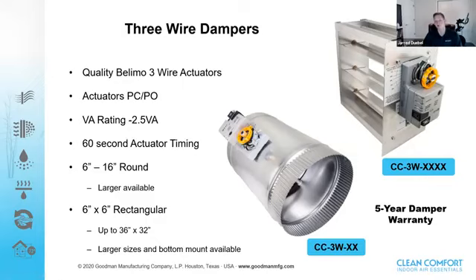part number CC-3W-1008-BM for bottom mount. So on all the standard dampers, you can always assume that the motor is going to be mounted on the smaller dimension. So again, on a 10x8, the motor is going to be mounted on the 8-inch side. On a 10x8-BM for bottom mount, it's going to be mounted on the 10-inch side.